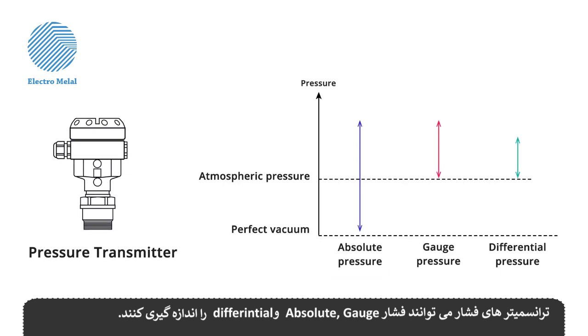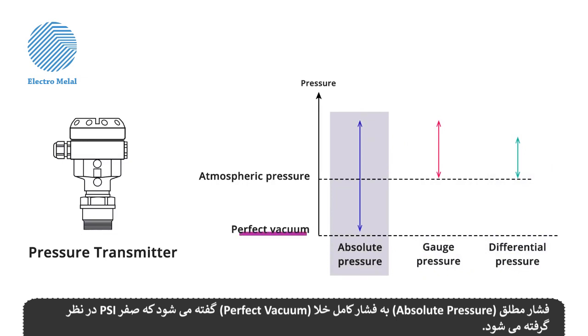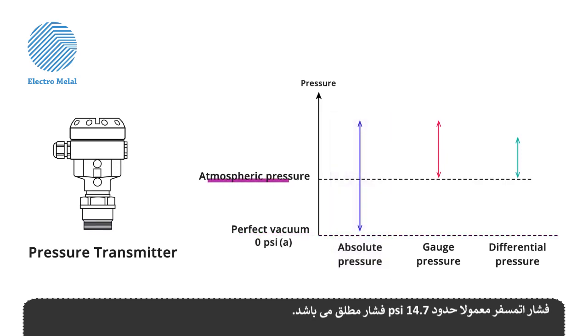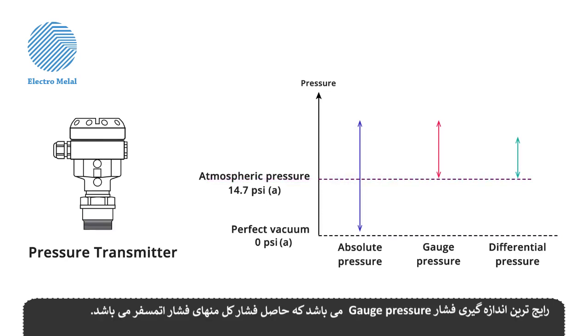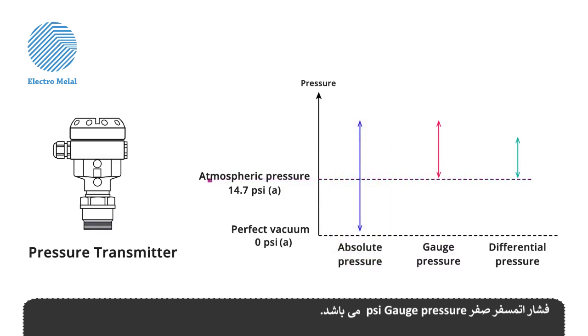Pressure transmitters can measure absolute, gauge, or differential pressures. Absolute pressure is referenced to a perfect vacuum, which is considered zero PSI. We express vacuum pressure as zero PSI absolute pressure. Atmospheric pressure is usually about 14.7 PSI absolute. The most common pressure measurement is gauge pressure, which is the total pressure minus the atmospheric pressure. Atmospheric pressure is zero PSI gauge pressure.